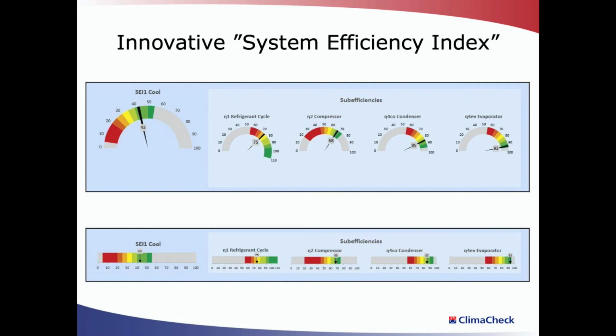Alternatively then, a new system efficiency index has been developed, which enables the performance of the system running at this moment in time to be compared with a perfect Carnot cycle. SEI then breaks down each component of the system to show you the performance of each and the overall system performance as well. So if, for example, the condenser is not working very well, this will also be reflected in poor compressor efficiency and performance, and the overall system efficiency will be down.